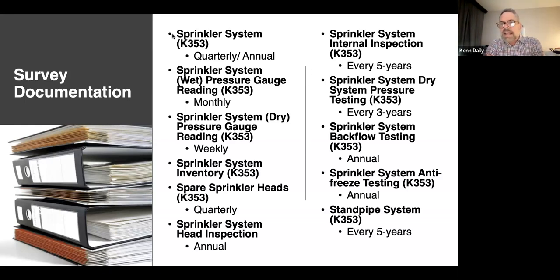If you are a facility that has antifreeze in your wet sprinkler system to ensure that it does not freeze, then that testing is done annually. That'd be specific gravity. That's the percentage of propylene glycol or glycerin in your system, and the specific temperature that your system would be rated to. Most of Pennsylvania is between -0 or -5 to -20. Should be rated to that.